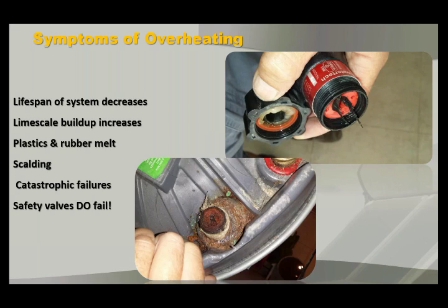I mean, yes, some of them can handle it, we're talking copper pipes that can handle high temperatures, but some of these components, like that plastic valve over there, were never designed to handle 130-degree water. With the temperature increase, the rate of limescale buildup increases. So look at that bottom picture. That's a TP port. That small little black dot in the middle is actually the probe of the TP. You'll see the TP just now.